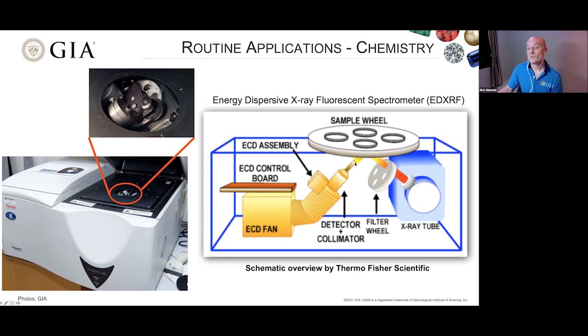So it's very important really to know that the tube and the detector, they have lifetimes and they need to be replaced every now and again. But the actual window of the detector is actually very, very fragile, and it has a beryllium window on it. And if this is broken at any time, then we have to replace the whole detector. So this is one critical factor.